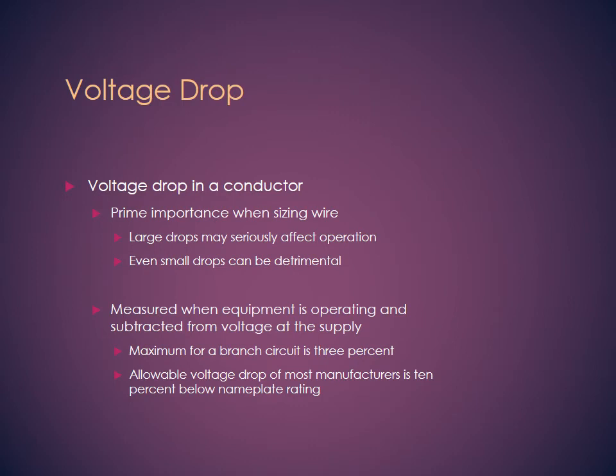Voltage drop, again, we talked about that already. Even a small drop can be detrimental, depending on the length, especially when you go with control, where you have to calculate the millivolts. If it's a large drop, you're not going to be able to turn that motor or that pump. If it's small, you might have issues with control depending on the sensitivity of that control. So that's basically one of the main reasons we need to do voltage drop. What you also would like to remember is that 3% is the maximum drop as a general rule for a branch, meaning from the main. I'll explain now.